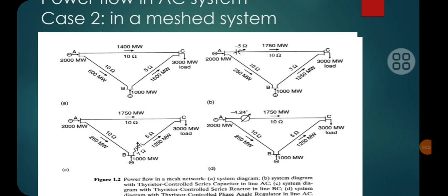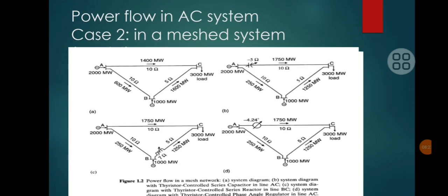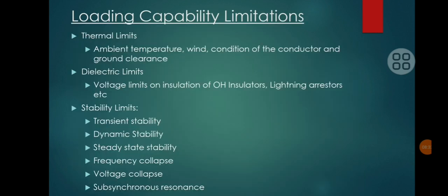In addition to what is not shown in this slide, we can achieve power flow control by injecting a voltage in a transmission line. These are the loading capability limits of a transmission line: thermal limits, dielectric limits, and stability limits. Stability limits are classified into many types based upon the time frame: transient stability, dynamic stability, steady state stability, frequency collapse, voltage collapse, and subsynchronous resonance. These are a few parameters which we will try to improve by incorporating FACTS controllers in the power system.